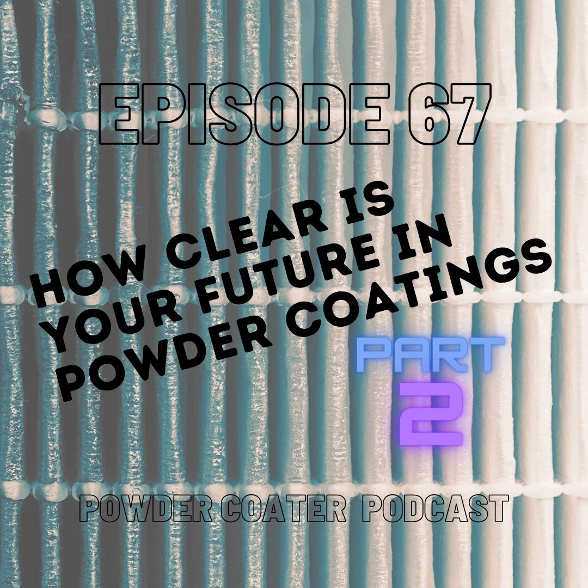What about drag out? Can you explain what drag out is? So this is going a little bit more into the sustainability side of it, not just carbon reduction. Drag out is when you're in stage 1 and you drag your chemistry into stage 2, then you have to dump your tank. People love to do this, and I understand why: your washer, a flow-through washer, was originally designed for a 6-foot long part. Now your business has changed and you want to run 8-foot long parts. But when you do that, your drain backs are supposed to be the same length as your longest part. It's just the 101 rule of washer design. So if you're running an 8-foot part on a 6-foot drain back, you're going to have issues of cross-contaminating all of your water.